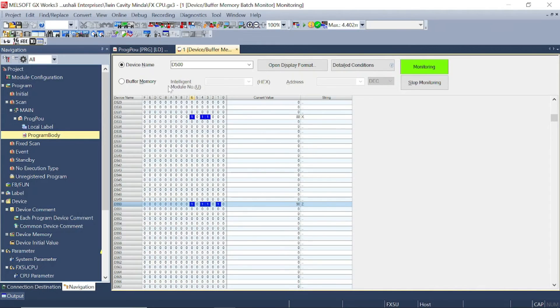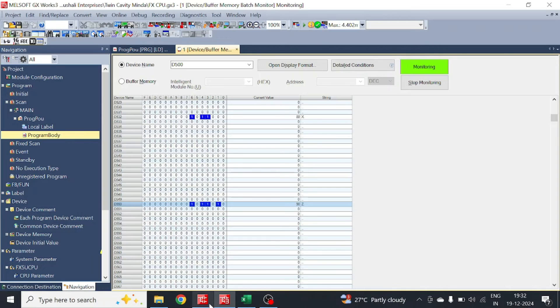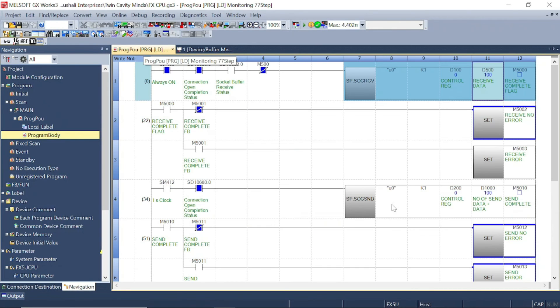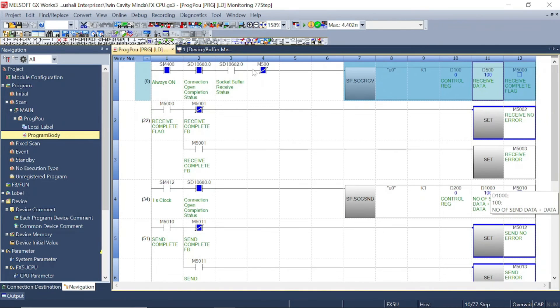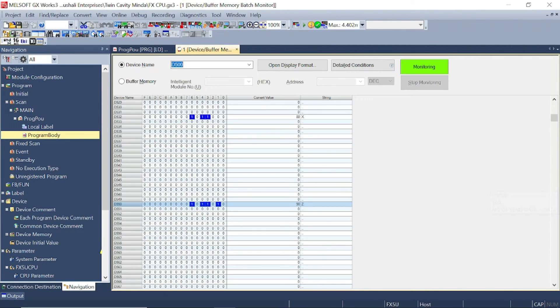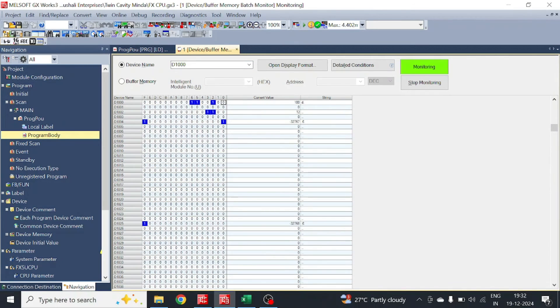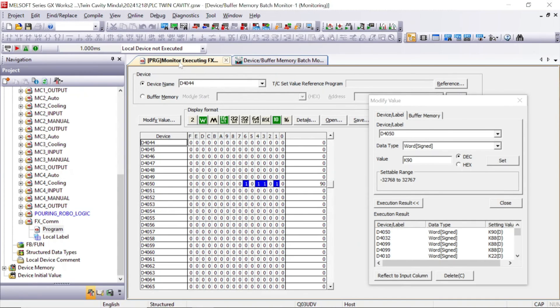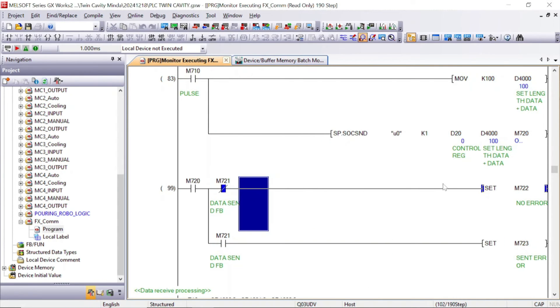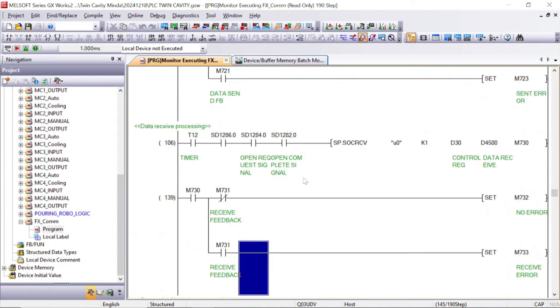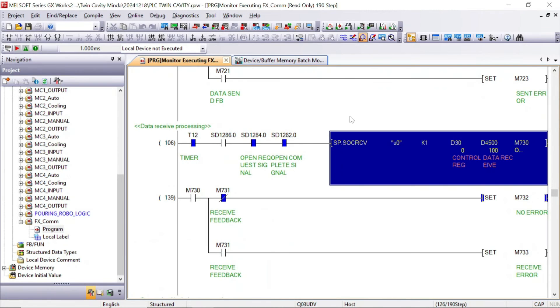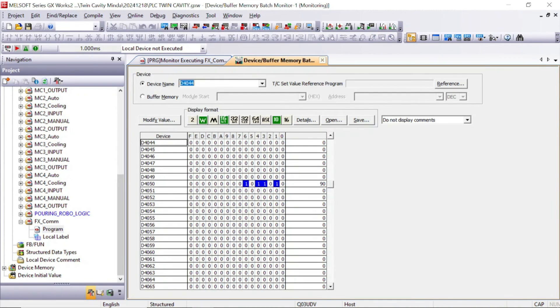In this way we can send data from Q series to FX5U. Now let's check vice versa — from FX5U to Q series. In FX5U, we will put a value in D1000. In Q series, the data will be received in D4500, as seen in the socket receive instruction.